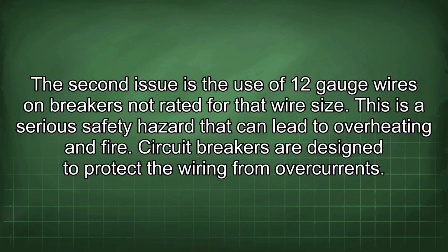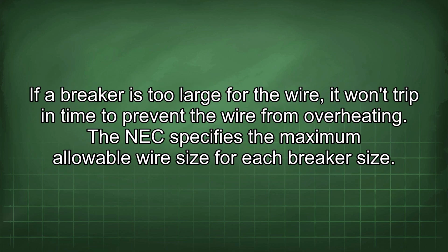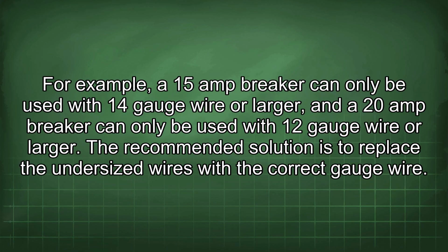The second issue is the use of 12-gauge wires on breakers not rated for that wire size. This is a serious safety hazard that can lead to overheating and fire. Circuit breakers are designed to protect the wiring from overcurrents. If a breaker is too large for the wire, it won't trip in time to prevent the wire from overheating. The NEC specifies the maximum allowable wire size for each breaker size. For example, a 15-amp breaker can only be used with 14-gauge wire or larger, and a 20-amp breaker can only be used with 12-gauge wire or larger.